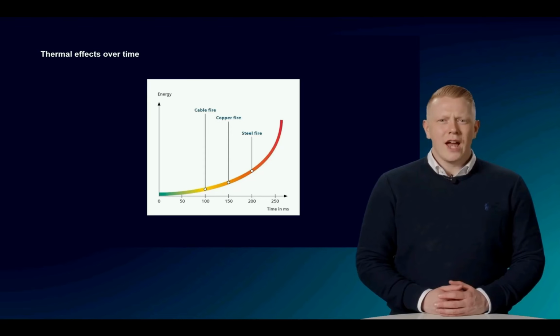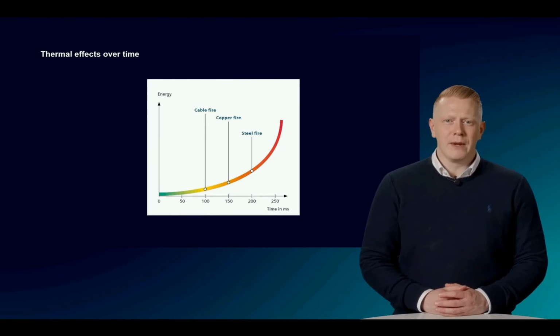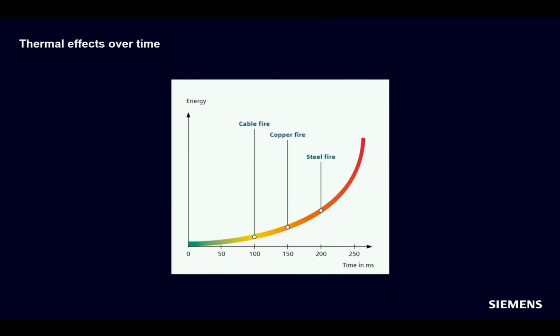In the last section, we discussed how we can use passive and preventive measures to limit or even avoid an arc fault. However, when limiting the arc fault with the help of passive measures, an arc flash burning time of 300 milliseconds can be expected. This duration in an event such as an arc fault also means a very high energy conversion. Let's recall the graph on the thermal influence that we presented to you at the beginning of the webinar. We see that there is an increased risk of fire beginning in the range of temperature rise from approximately 100 milliseconds. Due to the exponential increase, the risk of damage is increasing with every millisecond.